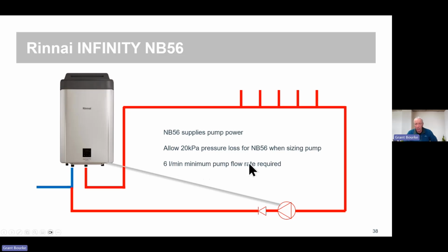But we need 6 litres a minute, or the pump or the unit won't fire. So you might end up with some bit of 20 mil return pipe at times in order to keep your flow velocities within those required limits. And when you're sizing that pump, you need to add an extra 20 kPa for the pressure loss through that unit, and the pump is driven from the NB. So again, we've got lots of drawings on how to do that.